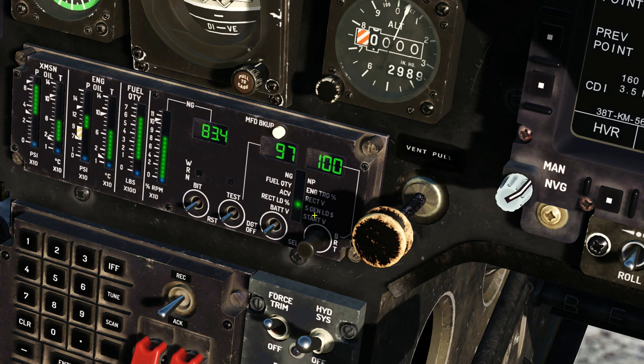My rectifier load percentage should be 97%. Now this right here should drop off, because my start generator, otherwise known as my DC generator, is now no longer doing anything except charging the battery. So once my AC generator kicks on, this will drop to about 12% or so. We'll fix this number too, just for immersion.